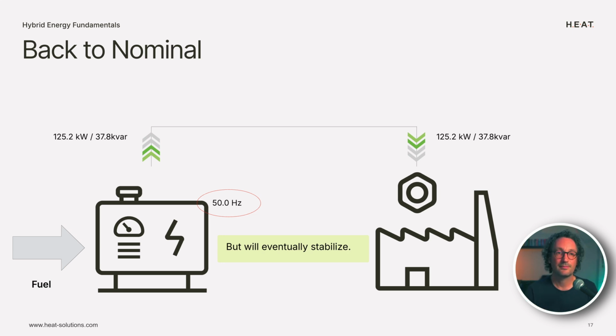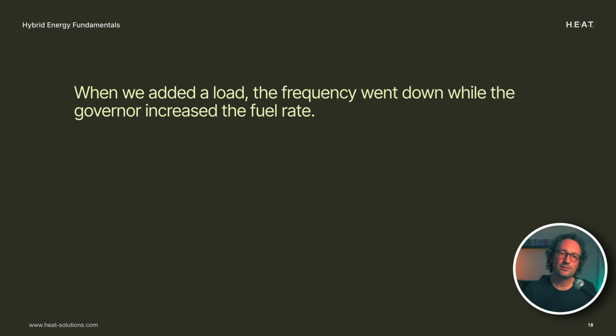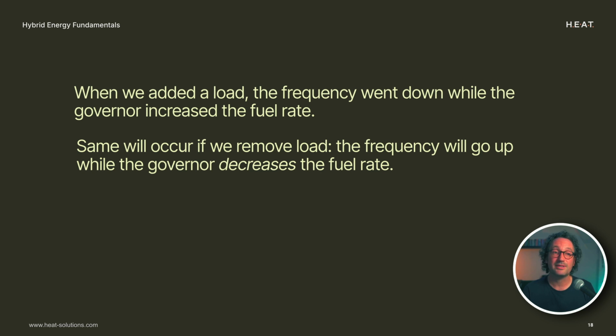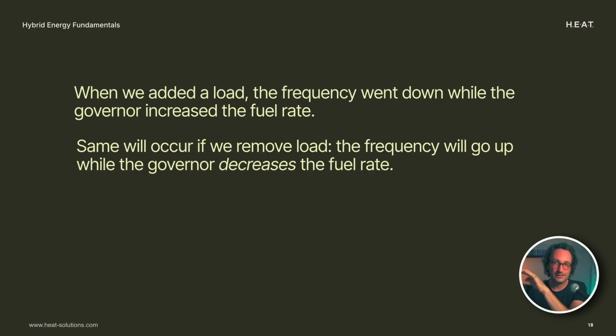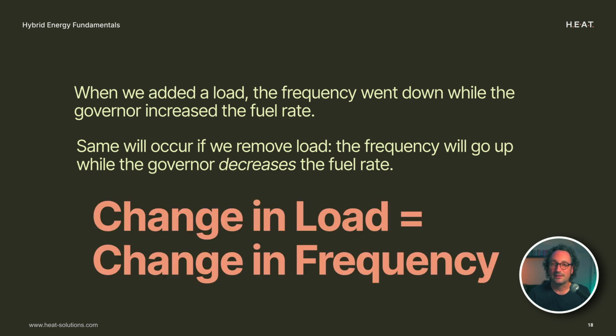So when we add a load, the frequency goes down, while the governor increases the fuel rate. And the same thing's going to happen in the other direction. If we remove a load, the frequency will spike up, and the governor will respond by decreasing the fuel rate until we find 50 hertz again. And this means, in general, that we should understand now that changes in load result in a change in frequency.